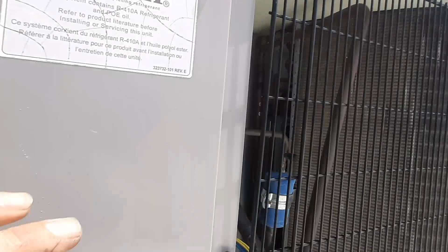to find out where my problem lies. I'm not getting any shorts to ground on my fan motors, any of these contactors. I'm not reading anything to ground. So that doesn't help me any. So we're gonna have to trace my wires. I'll get the back panel off and see what's down at the other end. Like I said, I've seen them rub out here before. There's 2 spots right there that I can see that are rubbing, but they're not shorted out. You'll see a big old black spot when they short out.